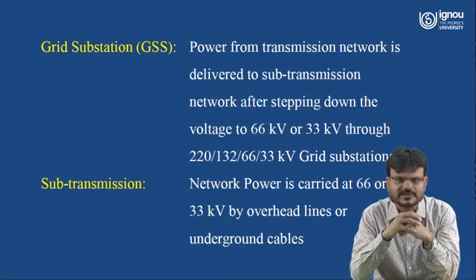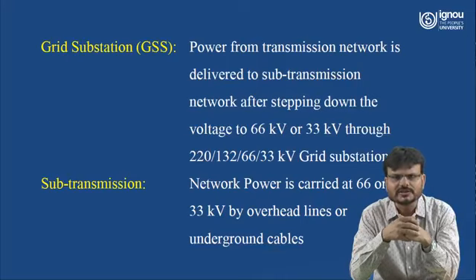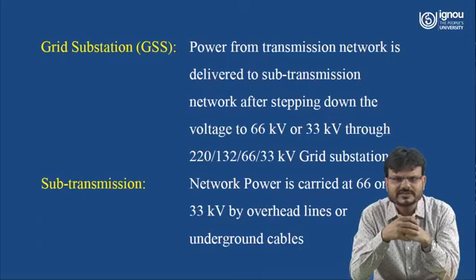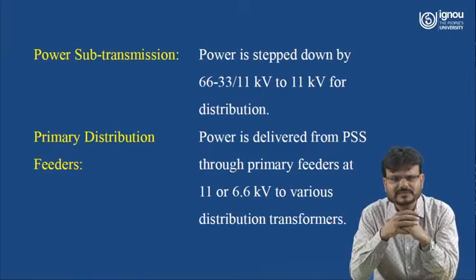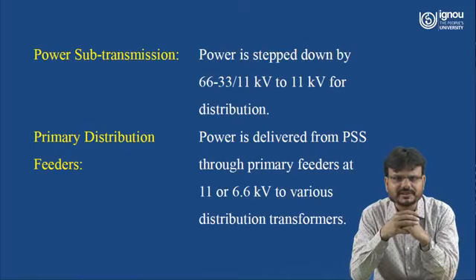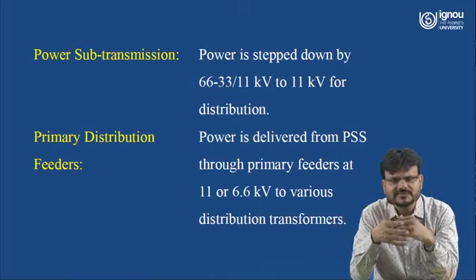There are different terminologies to understand. A grid sub-station is where power from the transmission network is delivered to the sub-transmission network, stepping down voltage to 66 kV or 33 kV through 220/132/66/33 kV grid sub-stations. Sub-transmission carries power at 66 or 33 kV by overhead lines or underground cables. In a power sub-station, power is stepped down from 66 or 33 kV to 11 kV for distribution purposes. A primary distribution feeder delivers power from the power sub-station through the primary feeder at 11 kV or 6.6 kV to various distribution transformers.